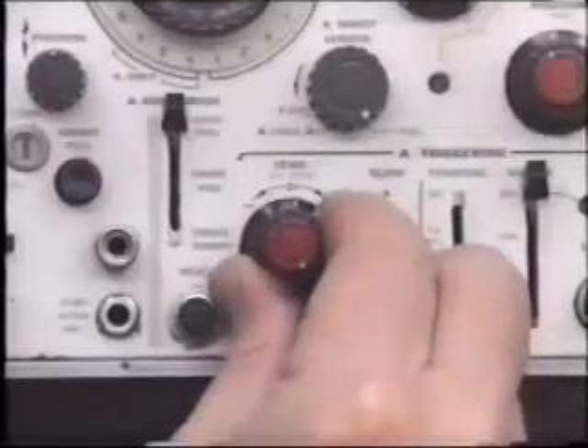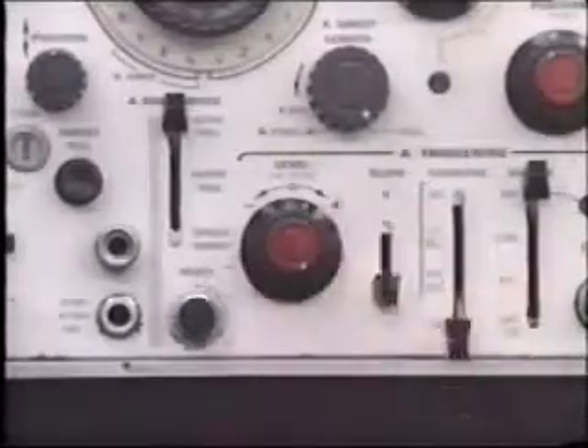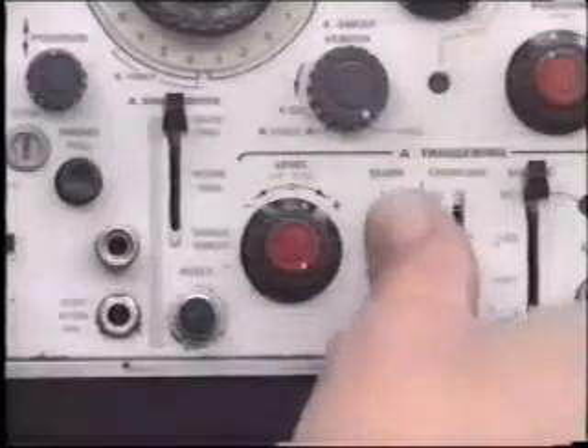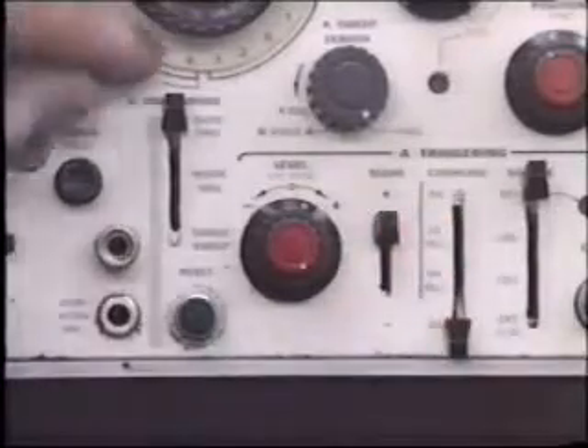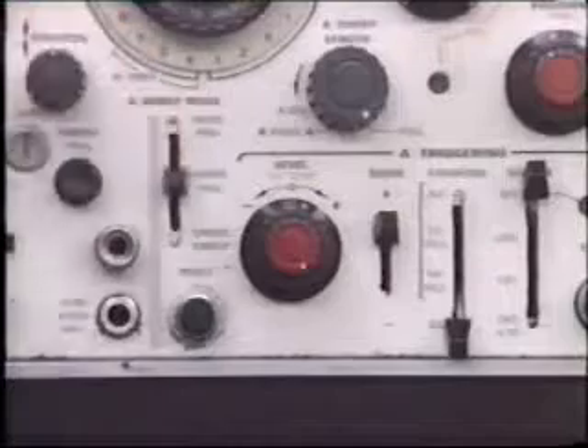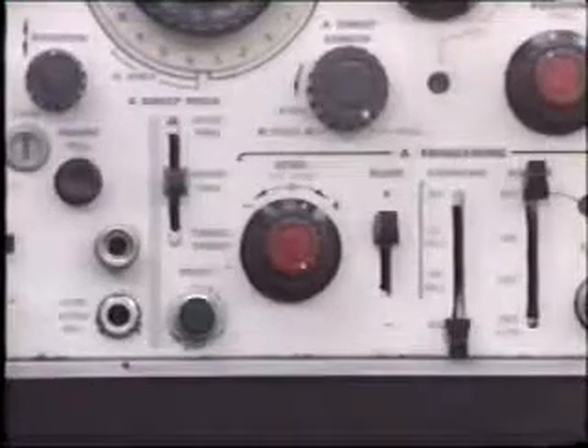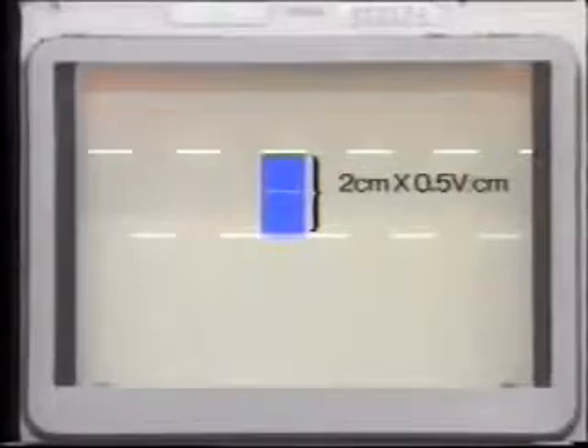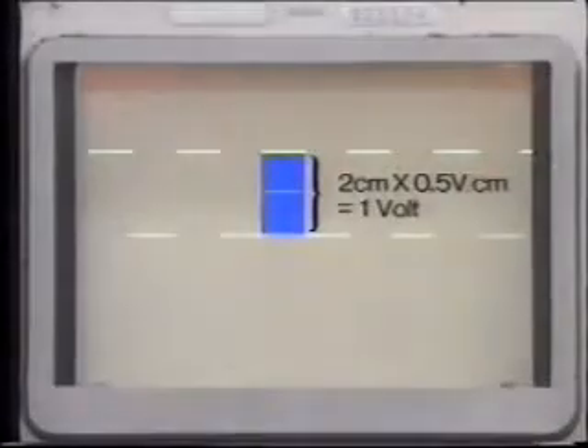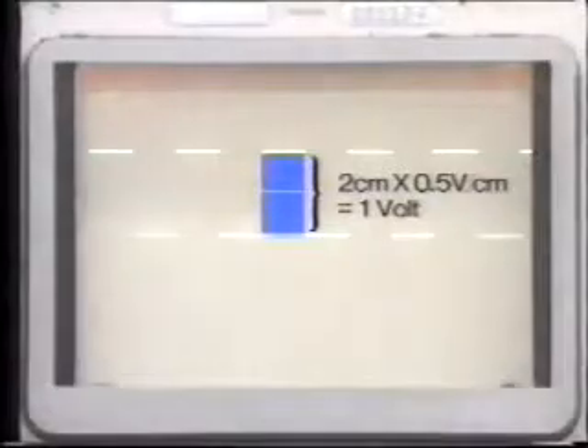At first, the waveform may be jittery or unstable. To improve this, we can adjust the trigger level and slope, positive or negative. You will also have to place the auto norm trigger mode in the normal position now that we have an input signal. So let's see what the display is telling us. In the vertical direction, we see 2 centimeters times 0.5 volts per centimeter, which equals 1 volt. This indicates 1 volt positive with respect to chassis ground.